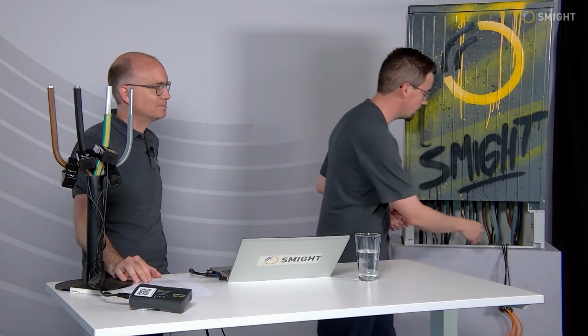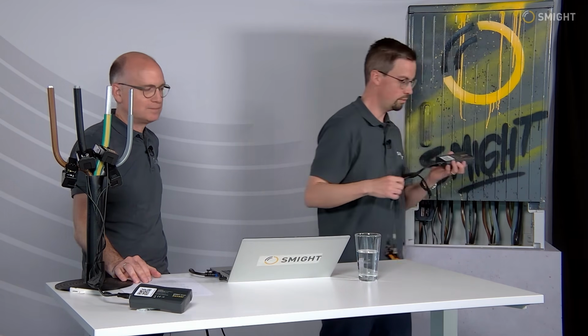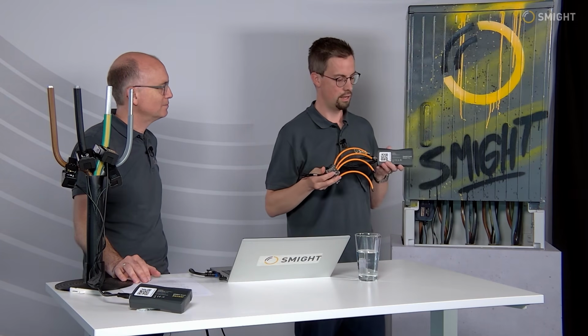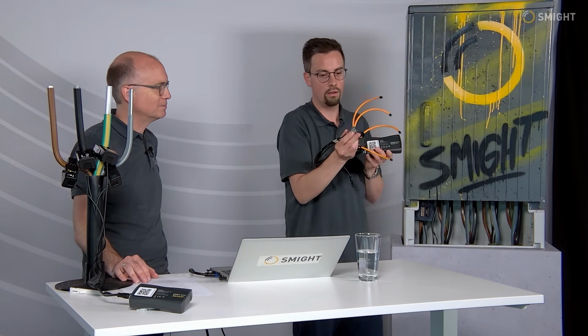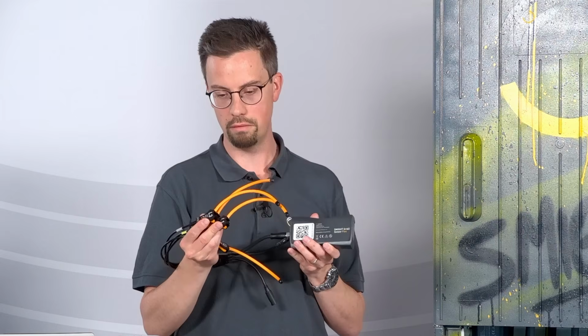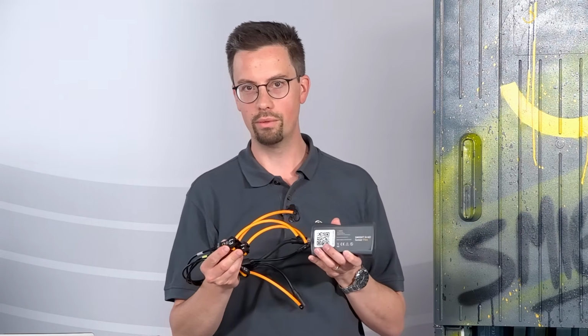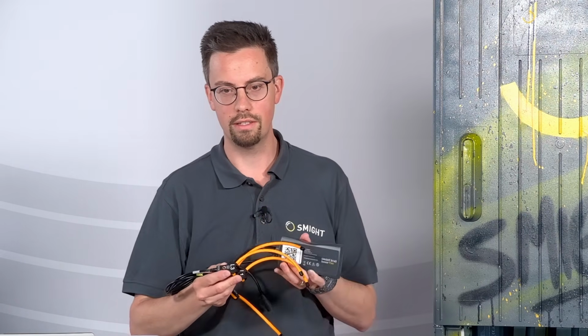In addition, we don't always have cables that are this thin - sometimes they're much larger. So we have a second solution, which we call our sensor flex. This solution uses Rogowski coils, which can be used for much larger diameters, and also in much tighter situations.